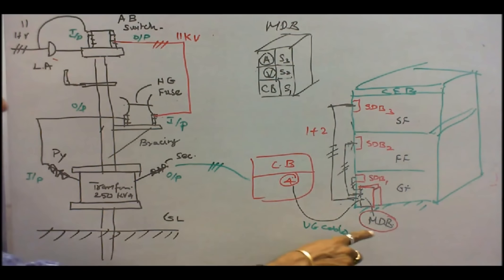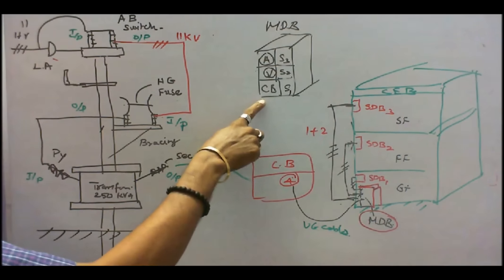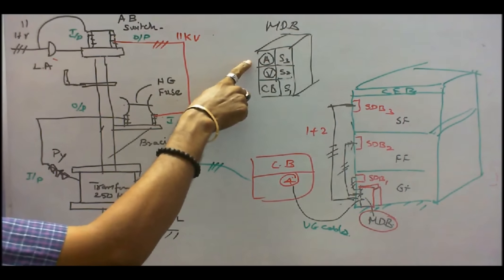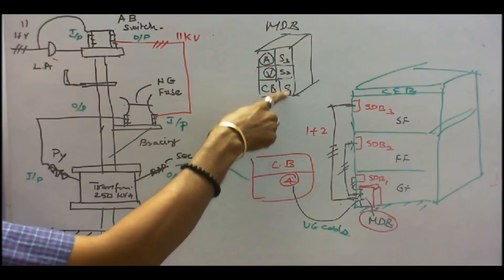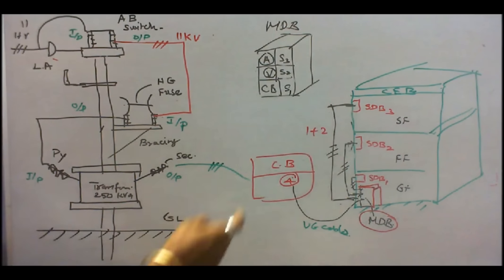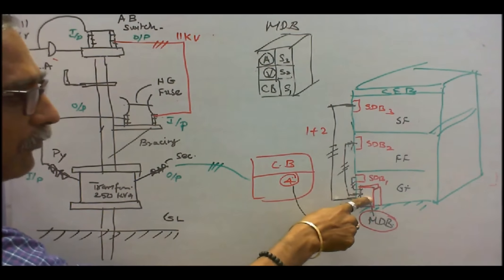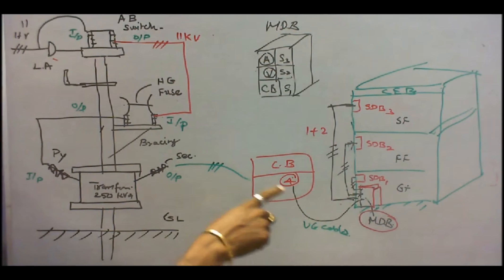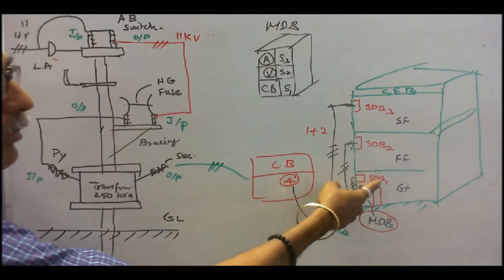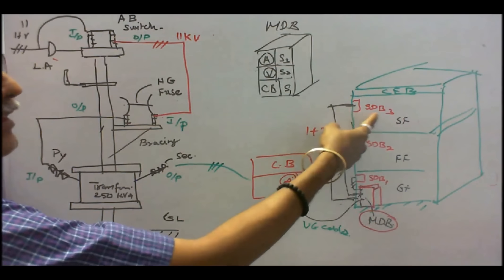The main distribution board is placed in the ground floor. Here the main distribution board acts as a distributor. In the main distribution board, I have a circuit breaker and panel board voltmeter and ammeter. And these are all the master control switches S1 for ground floor, S2 for first floor, S3 for second floor. Now, from the main distribution board, I am feeding power to the sub distribution boards, that is SDB1, SDB2 and SDB3.